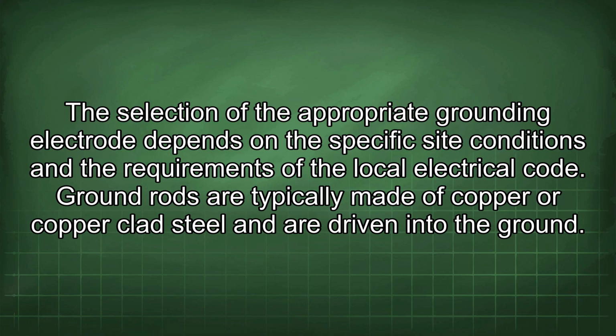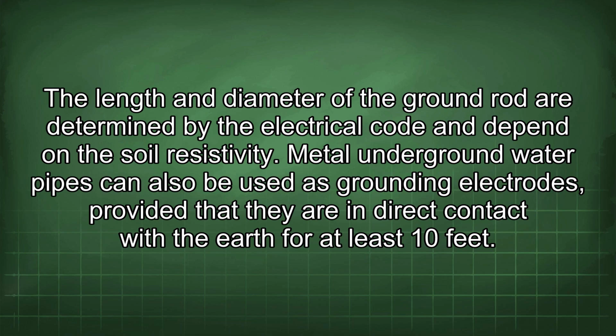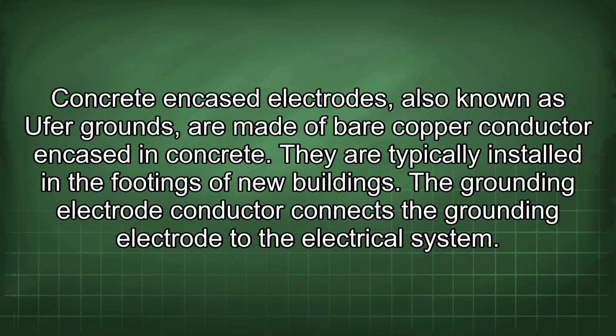Ground rods are typically made of copper or copper-clad steel and are driven into the ground. The length and diameter of the ground rod are determined by the electrical code and depend on the soil resistivity. Metal underground water pipes can also be used as grounding electrodes, provided that they are in direct contact with the earth for at least 10 feet. Concrete encased electrodes, also known as UFER grounds, are made of bare copper conductor encased in concrete. They are typically installed in the footings of new buildings.